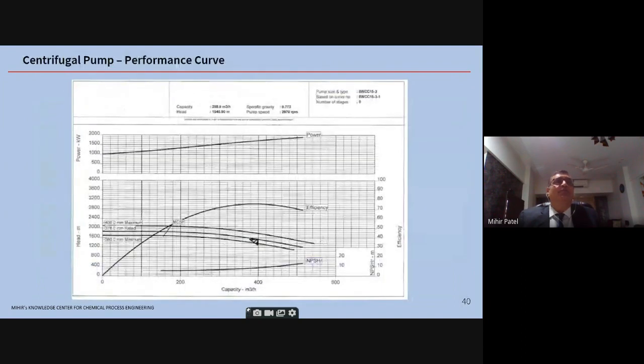Now, there's a typical performance curve of a pump. At the very bottom, we have the NPSHR, which rises as the capacity goes up. The shaded area is the design point. On each line, we have written the impeller diameter. Any casing has a maximum impeller diameter, so there is some flexibility of going higher in impeller diameter and head. If you are stuck, let's say, in detail engineering towards the end, you can go slightly higher on the head also. The efficiency curve is there, and the shaded portion is almost at the BEP, the best efficiency point.